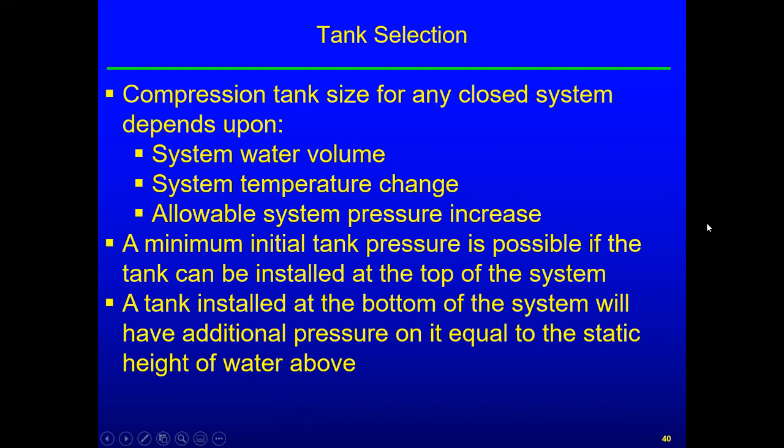And if it's cold water, it's 2.31 feet. Every 2.31 feet gives one PSI of additional pressure. If it's hotter water, it'll be a little bit less because hotter water is a little less dense. And you can multiply by the specific gravity to adjust for water temperature if you need to.